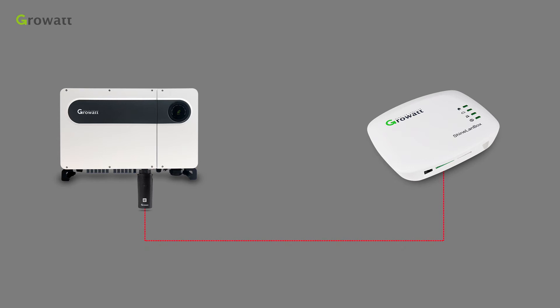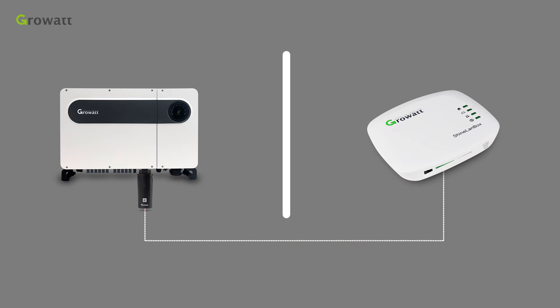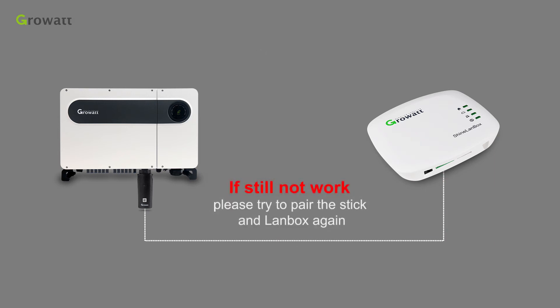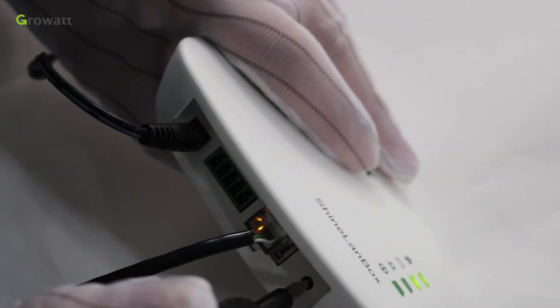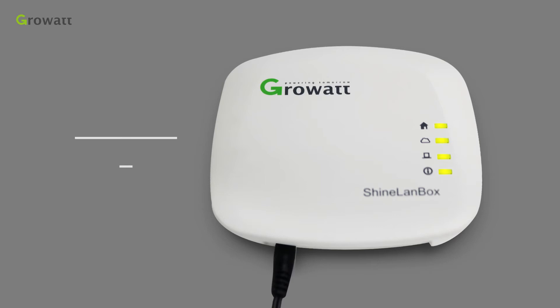The data collection interval of the system is 5 minutes. If you are not able to see any data for a long time, please carefully check the LED status and check the connection accordingly. If the connection is not stable, check the distance and whether there are any obstructions between the RF stick and the ShineLanBox. With one wall, the distance should not exceed 50 meters. With two walls, the distance should not exceed 20 meters. If it still does not work, try to pair the stick and ShineLanBox again. Press the pairing button of the ShineLanBox for more than 6 seconds until all 4 LED lights are on, then release the button and re-pair.